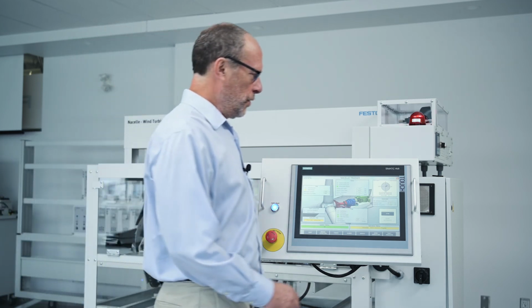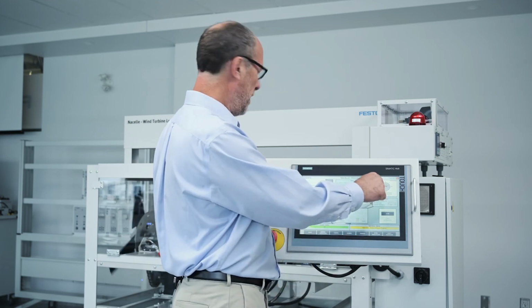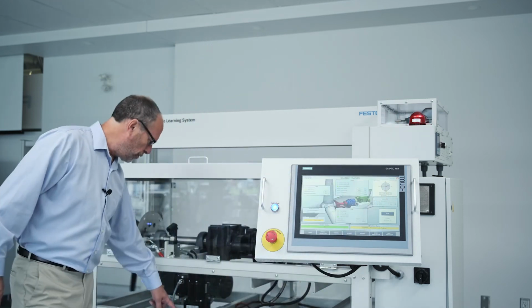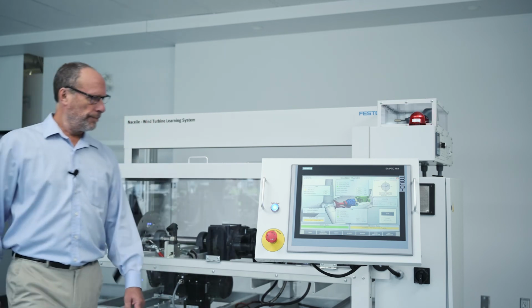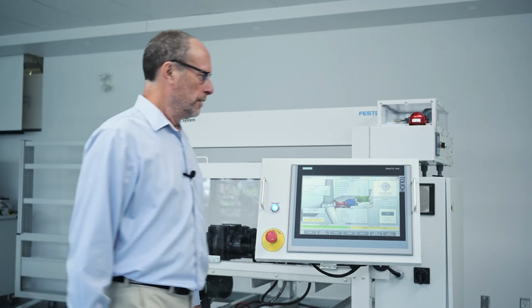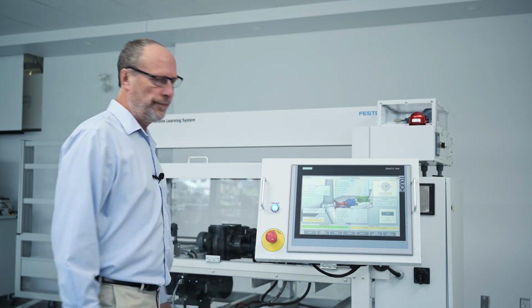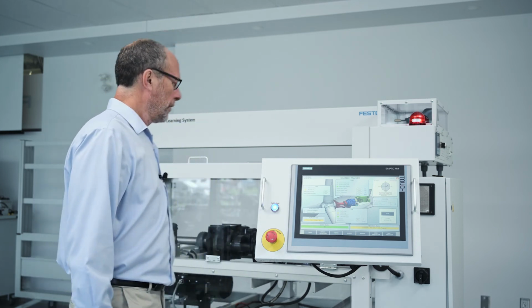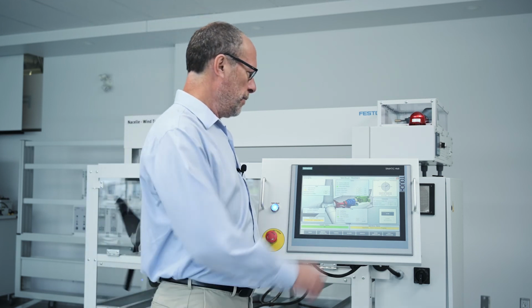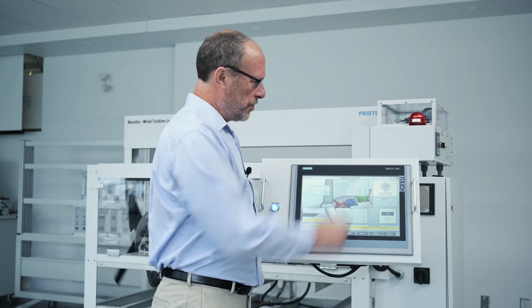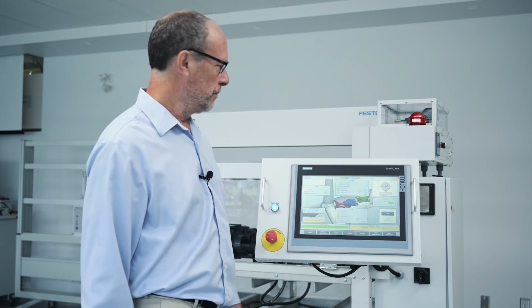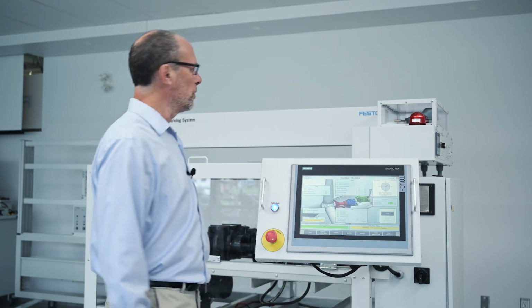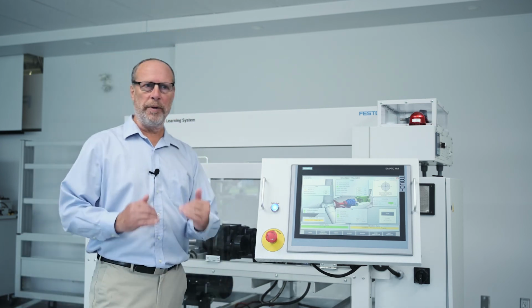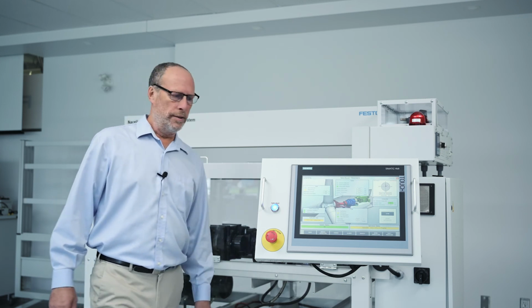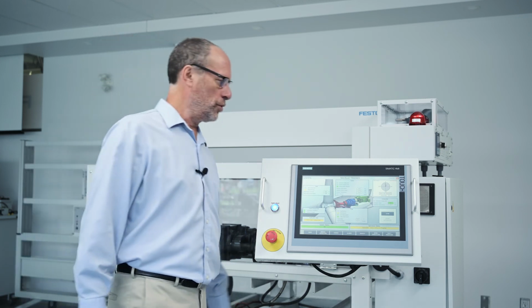Now we can look at the new wind condition that we have. You see the nacelle now needs to turn. Okay. Get in the wind. Get up to speed. And when we come up to the proper speed, the generator will start to get the power. So now we've got the power on to the grid. And we'll get to the third step where I've put very low speed condition for the wind so that the machine will not be able to supply power.